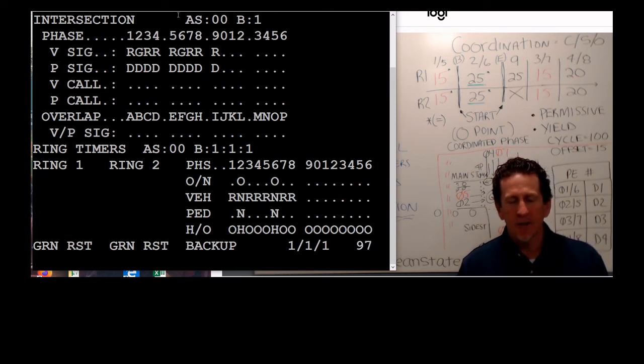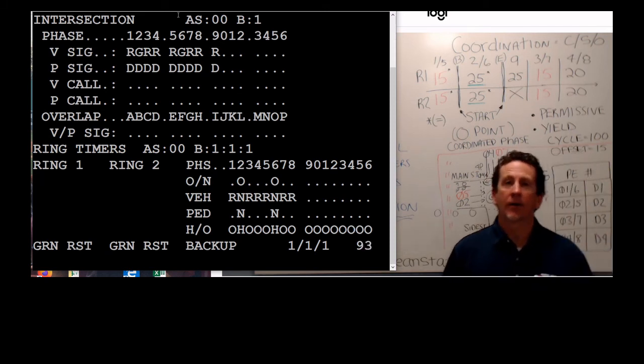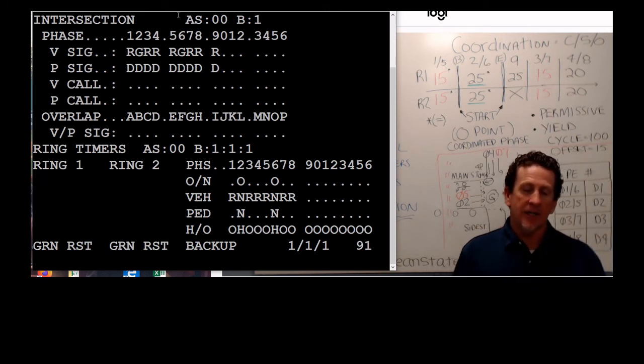And then the P call is PEDs. This is the number one troubleshooter when you have a bad PED button. Basically, somebody's going to get a call and say, the PED's coming in all the time. So I'm going to say, go to the screen, go FFF, go 17, and see the line that says P call? Do you have a constant call right there? Do you see a C on it?